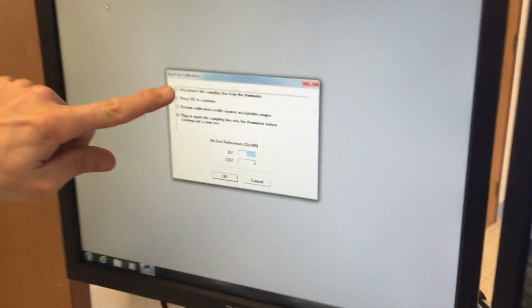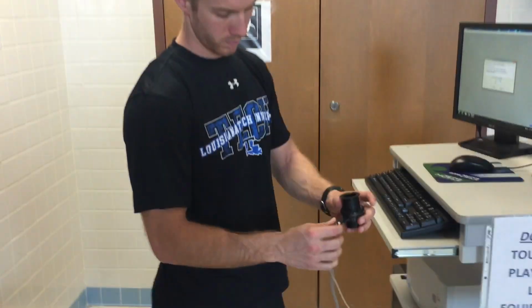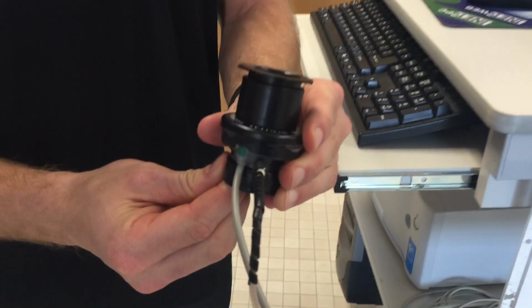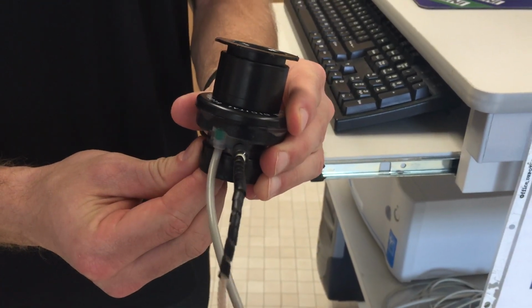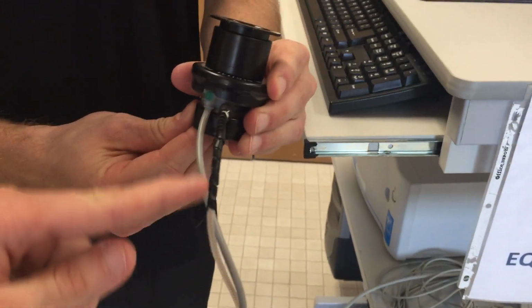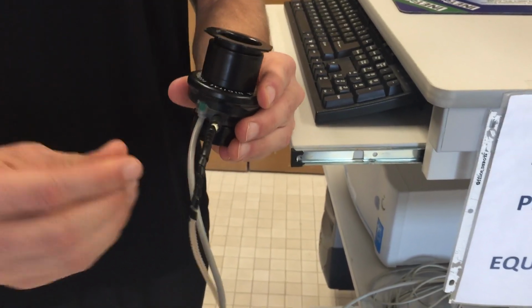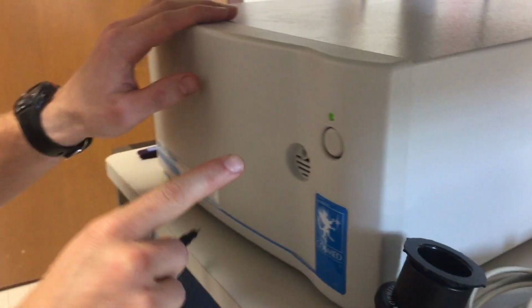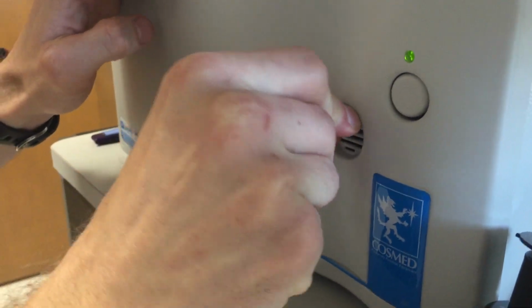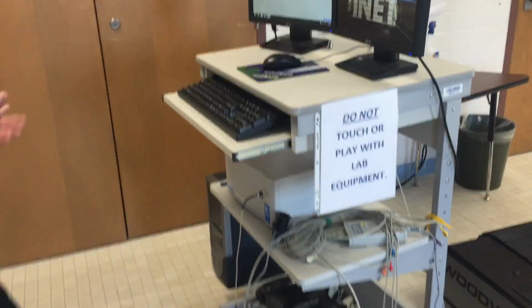Number one, it's going to say disconnect the sampling line from the flow meter. So what we need to do, we need to find the flow meter. If we zoom in close, we see that there's two cords attached to it. One gray and then one has the black piece on it that kind of leads into this clear tube. This clear tube is the sampling line. So when it says disconnect the sampling line from the flow meter, we're going to pull that out, and then we are going to connect it into the front of the CosMed unit. And we see the nice opening right there in the front. It sticks right in. Do not try and disconnect the gray tube from the flow meter. It will not come out. If we do, that breaks the unit. So make sure our flow meter is set nice and stable so it won't fall off.